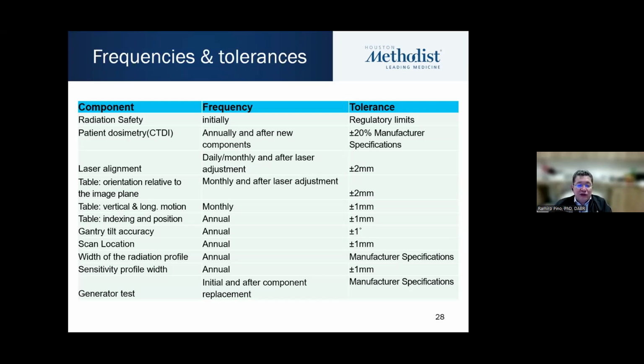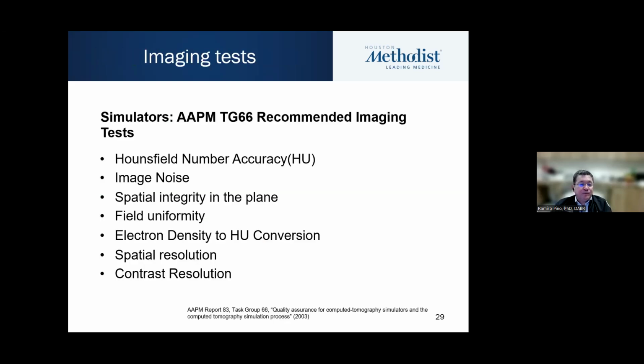The table orientation is important. It should be checked monthly, as well as the vertical and longitudinal motion. Indexing and positioning is checked annually, as well as tilt, scan location, the width of the radiation profile, and the width of the sensitive profile as well. And the generator test should be done initially and after every component replacement, but we typically do it also annually just to make sure that the tube is performing as expected.